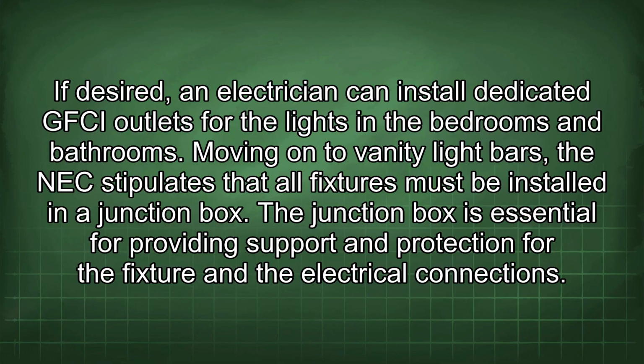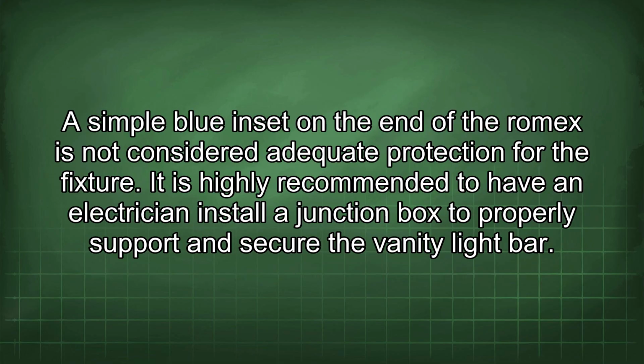Moving on to vanity light bars, the NEC stipulates that all fixtures must be installed in a junction box. The junction box is essential for providing support and protection for the fixture and the electrical connections. A simple blue inset on the end of the Romex is not considered adequate protection for the fixture. It is highly recommended to have an electrician install a junction box to properly support and secure the vanity light bar.